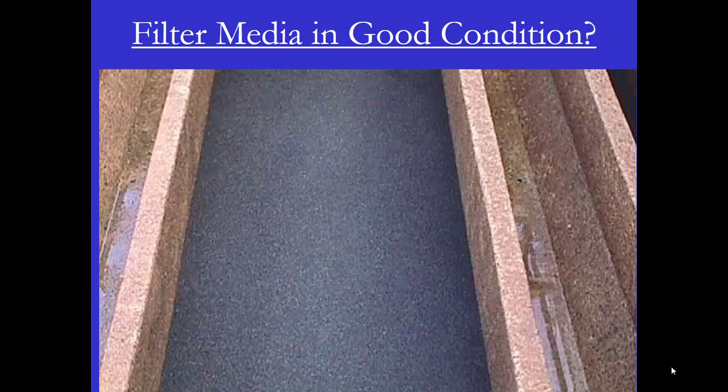If you look at a filter after it's been backwashed, it could appear to be in very good shape. The media is very level and there's no indication there's a problem with the filter. However, there might be multiple problems under the media.